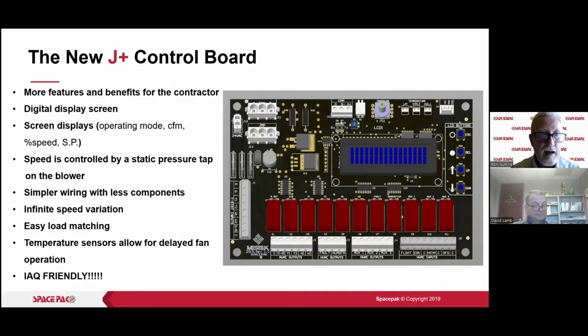So again, that was the J series. Now, the J plus series: again, we've got more features and benefits on this that you used to have to do manually, but now you can do through the board. We have a digital display screen. That's going to display operating mode, CFM, percent speed, static pressure. The speed can be controlled either by static pressure, or it can be controlled by percentage of speed. So for zoning, for instance, you can actually have the unit reduce its speed if you're transitioning to a single zone of operation.